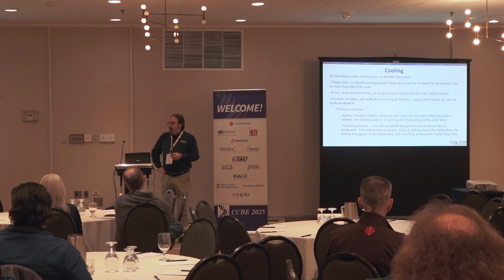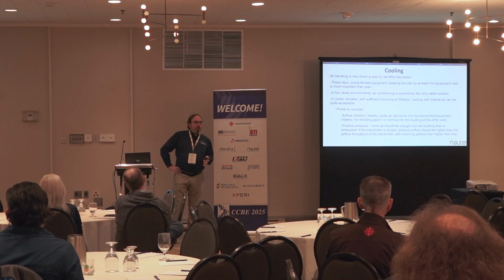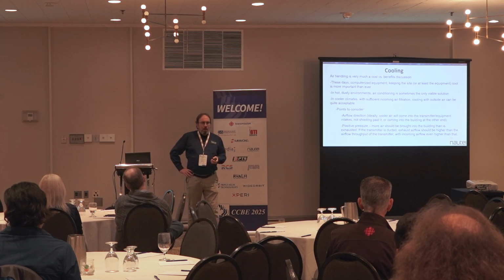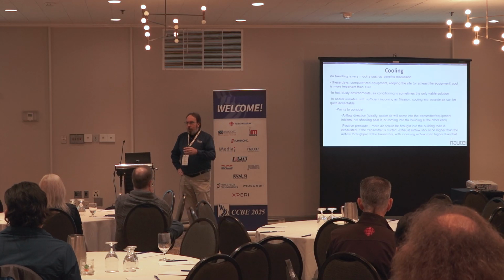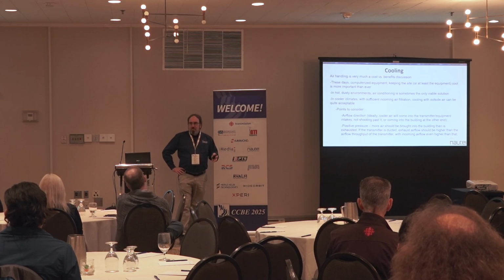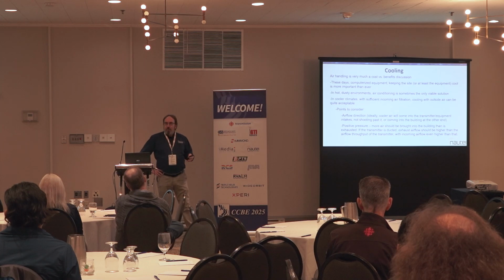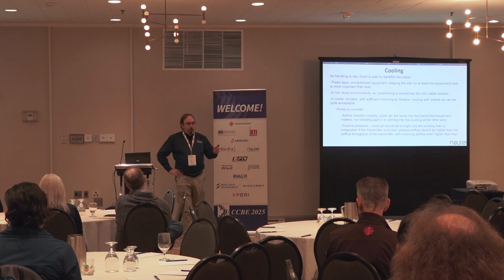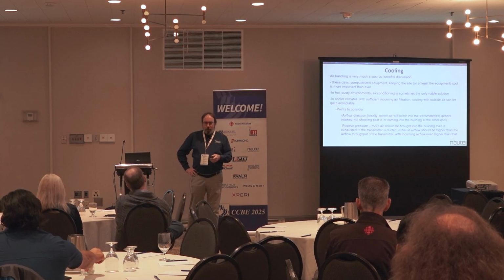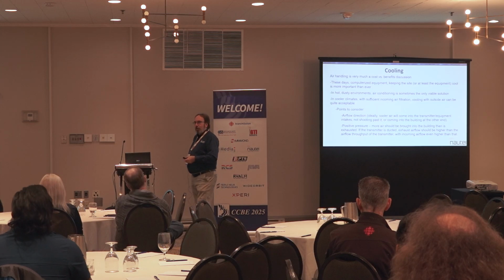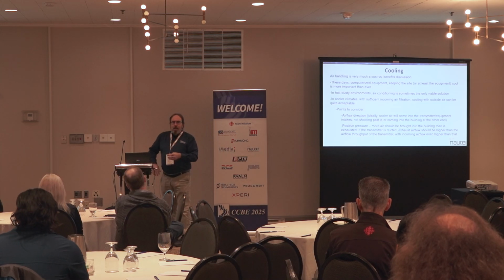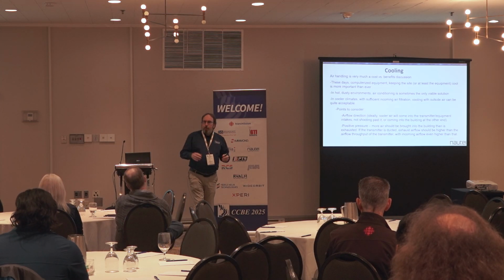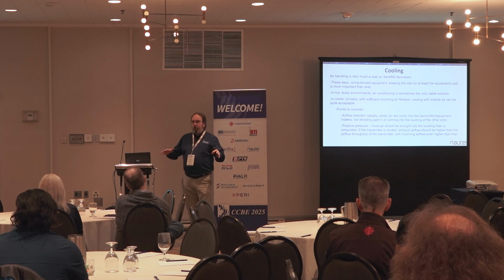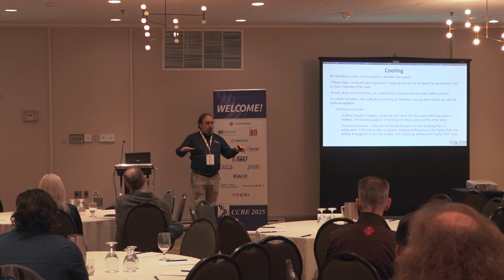So there's a lot of things you can do for airflow, but make sure the air goes through the equipment. I've walked into sites where the room, an air-conditioned room, was 5, 10, 15 degrees below room temperature, but the transmitter's overheating, because if you're not shoving that cool air through the transmitter... Here's the thing: most HVAC techs put in an air conditioner to keep the human in the room comfortable.